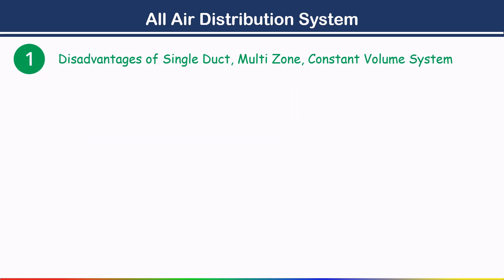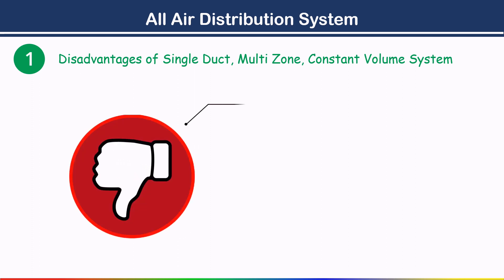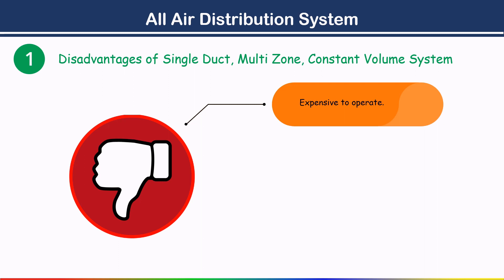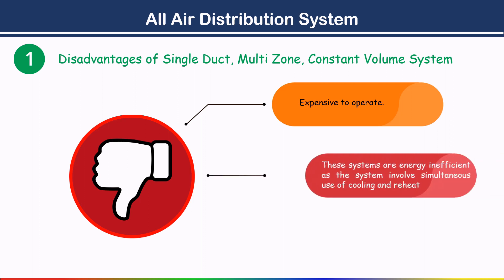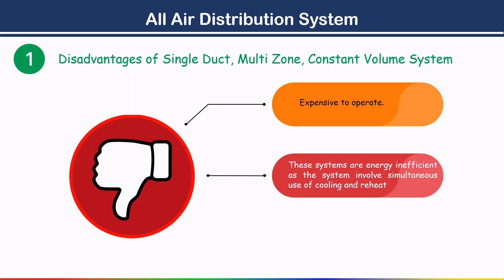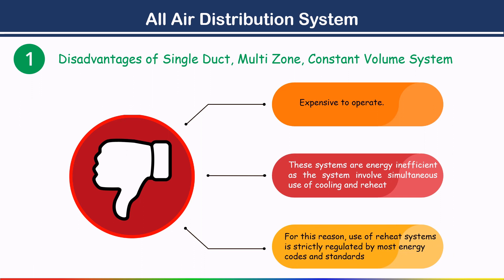Disadvantages of the single duct multi-zone constant volume system: first, it is expensive to operate compared to the single zone system. Second, these systems are energy inefficient as they involve simultaneous use of cooling and reheat. For this reason, use of reheat systems is strictly regulated by most energy codes and standards.